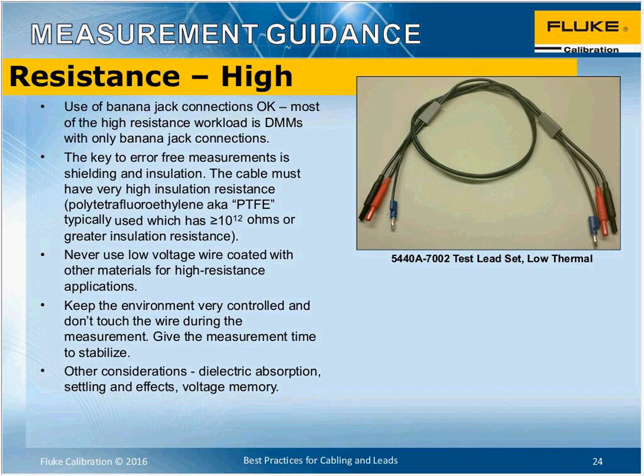A recent customer visit, just to share a story: they had problems with the resistance measurement stabilizing. Walking over to their laboratory and looking at the instrument, I could tell right away what the problem was. They were using patch cords without insulation and without a ground plug, and the measurement was all over the place. As soon as we plugged in the ground and used the right cable, the measurement stabilized right away. The takeaway was to invest in a good cable for that measurement. They spent probably a good 5 hours with a tech trying to figure out why the instrument wasn't stabilizing. So we do sell these cables. If you're interested, just send me an email after the webinar and I can help you obtain one.